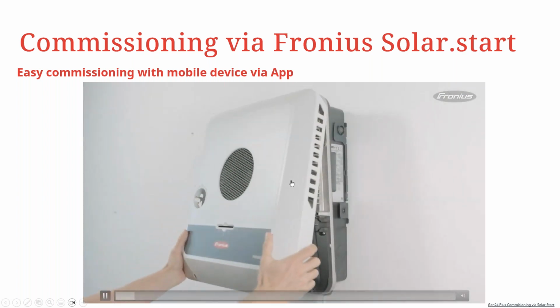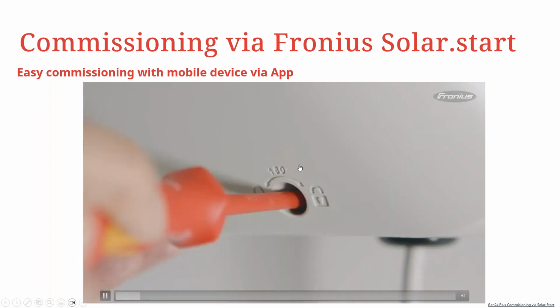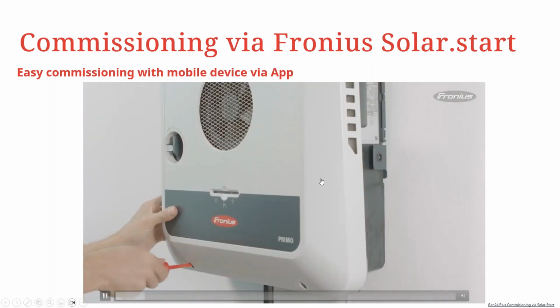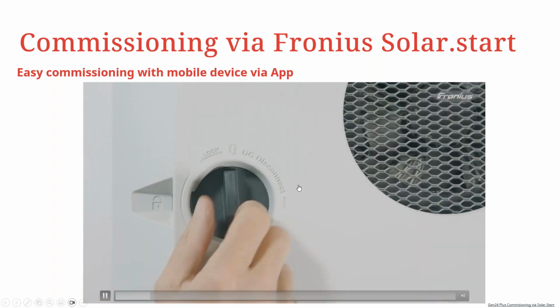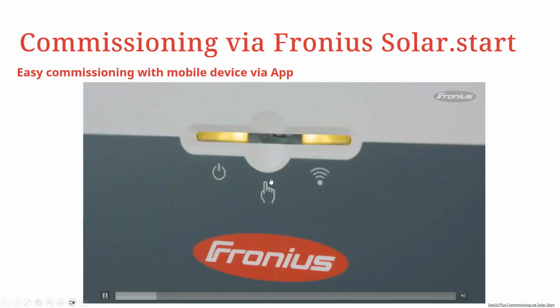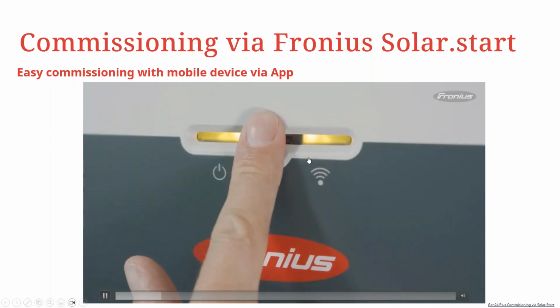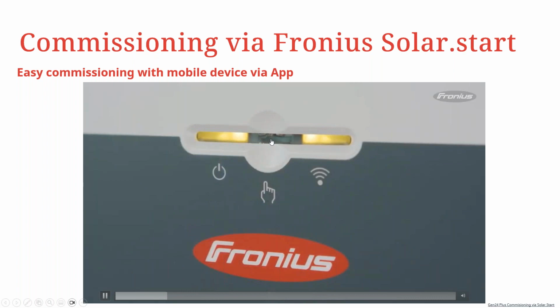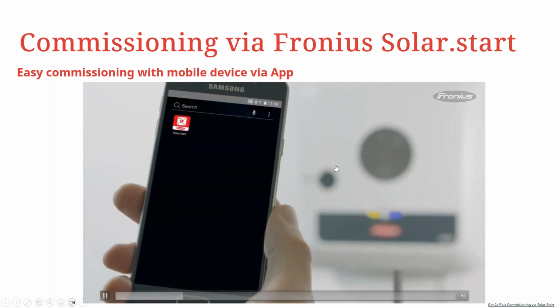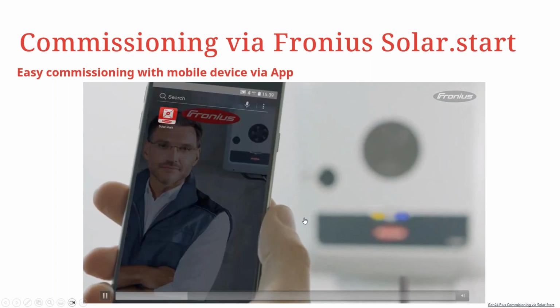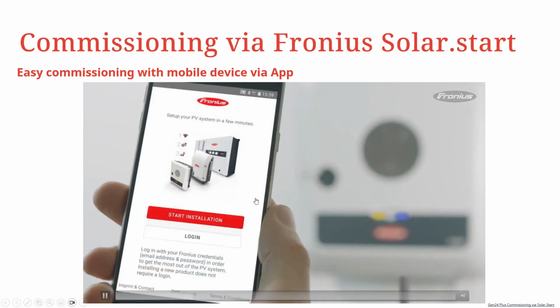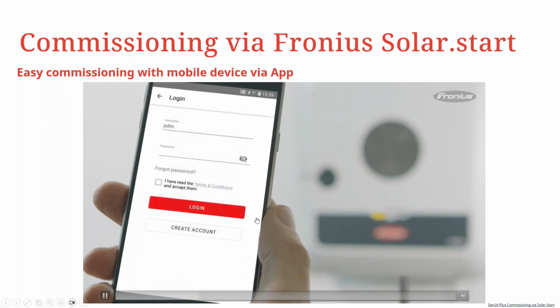So we can see how this is done. The DATCOM cover and the inverter cover are put in place, and then the DC disconnector switch is put on position 1. The touch sensitive button is pressed for approximately 1 second. You can now see that the communication LED is blinking. Next up, we download our SolarStart app and then start the installation process.